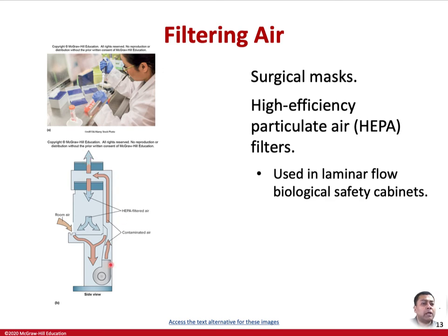So this is the working of a laminar airflow hood, where you can use some of the pathogens behind this airflow hood, and it keeps the personnel who are handling the microorganism completely safe, and also keeps the laboratory or the environment safe, so that these microorganisms cannot come out of these laminar airflow hoods.